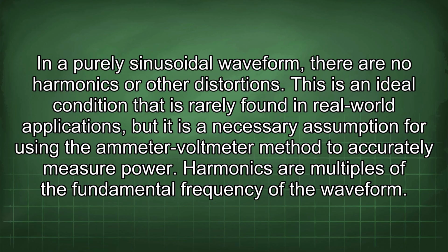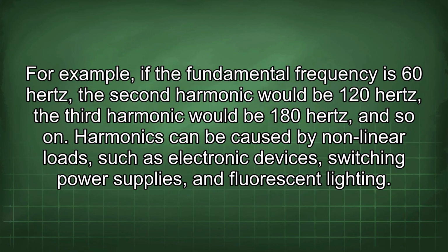This is an ideal condition that is rarely found in real-world applications, but it is a necessary assumption for using the ammeter-voltmeter method to accurately measure power. Harmonics are multiples of the fundamental frequency of the waveform. For example, if the fundamental frequency is 60 Hz, the second harmonic would be 120 Hz, the third harmonic would be 180 Hz, and so on.